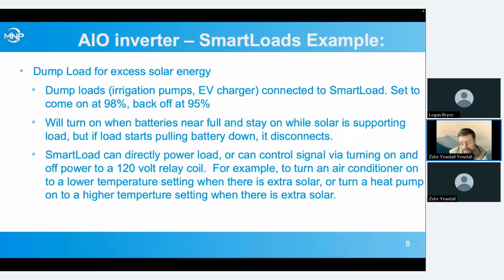We could also do a heat pump, same thing, dump extra solar into the heat pump, maybe bring the space up to 75 degrees instead of 60 something when we've got that extra solar. And then later in the evening, we can kind of coast a little longer because we've heated the space up a little more. In those cases, you don't really want to be just turning power on and off to the air conditioner or the heat pump, but using this interface relay to get into the thermostat system of it and turn it on and off that way can be a better option.